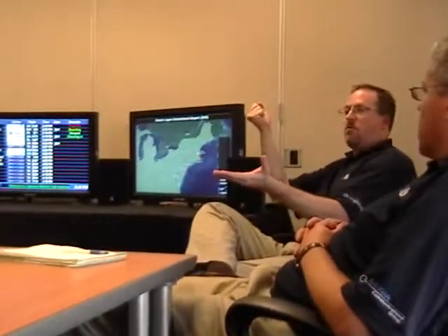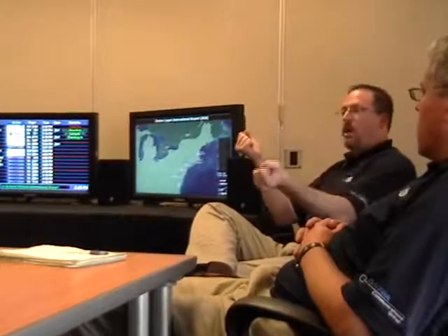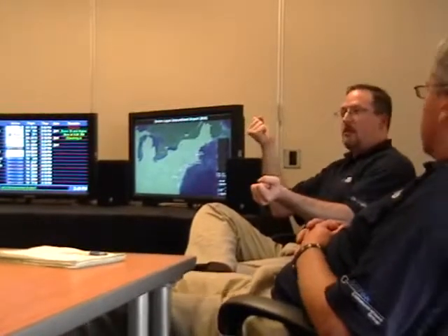Or you can press the mic and record while you're talking, and then when you release the mic switch, it goes ahead and plays the announcement. Right. In that case, where you have two right next to each other, if one picks up the zone before the other does, it'll hold that other announcement and preempt it. And then when the other's done, it'll go ahead and play the next announcement. That's if it's recorded, yeah. So therefore, you've got intelligibility on both sides. We do that at PFW.